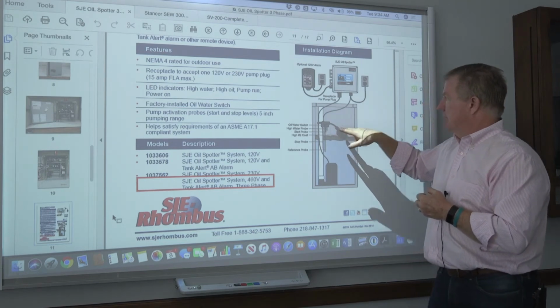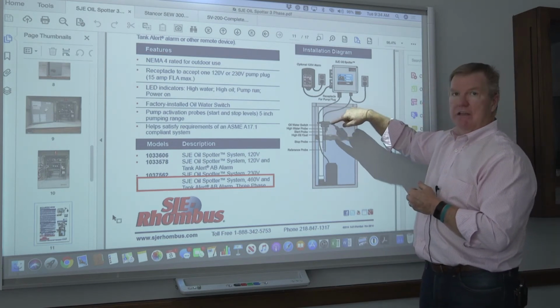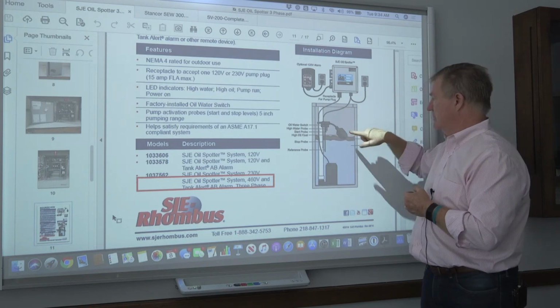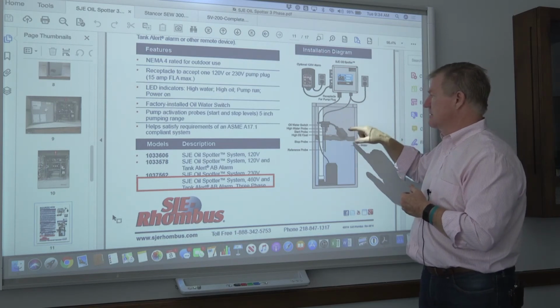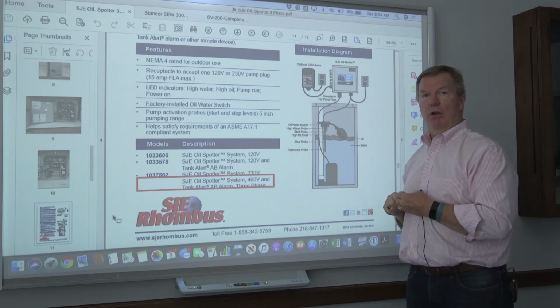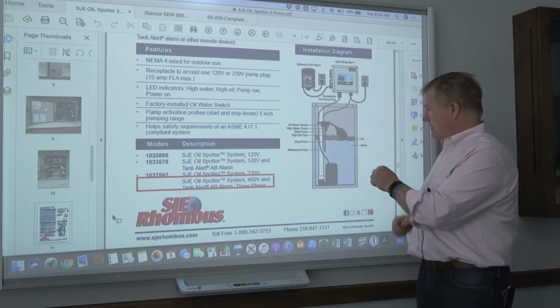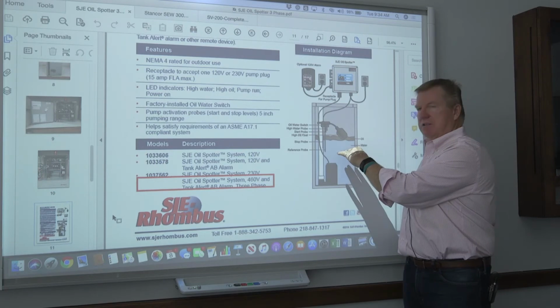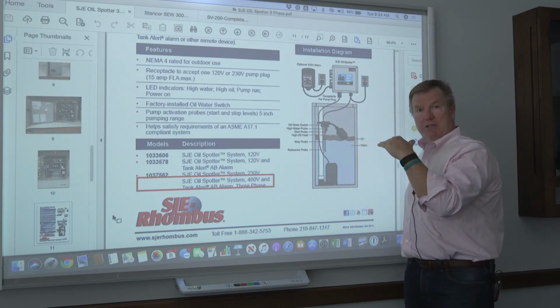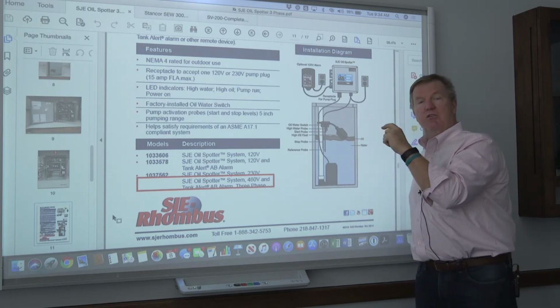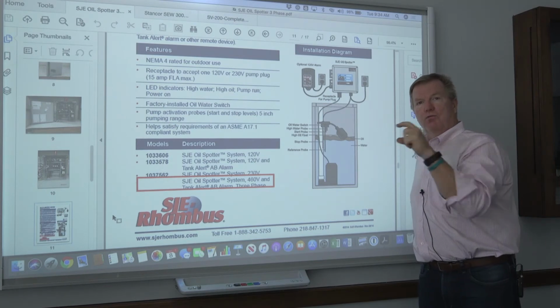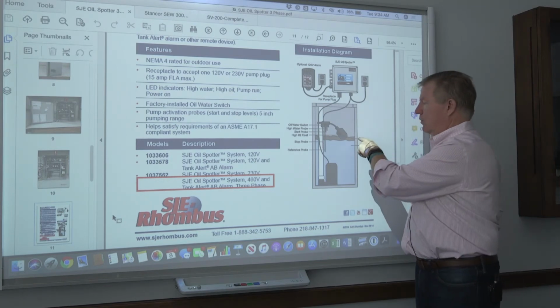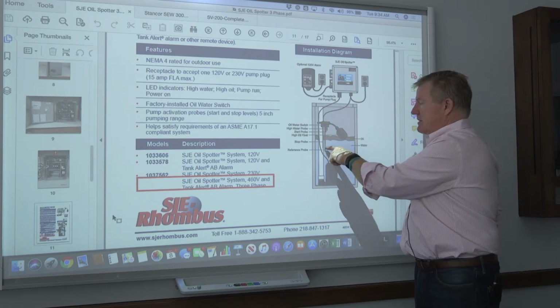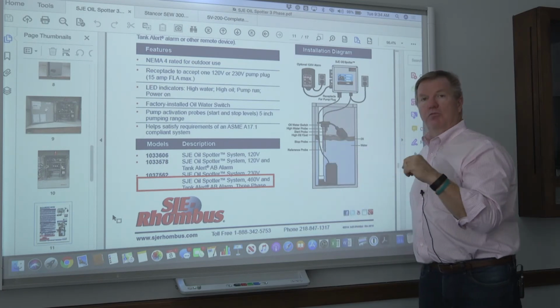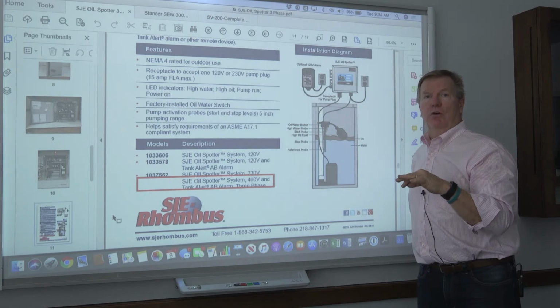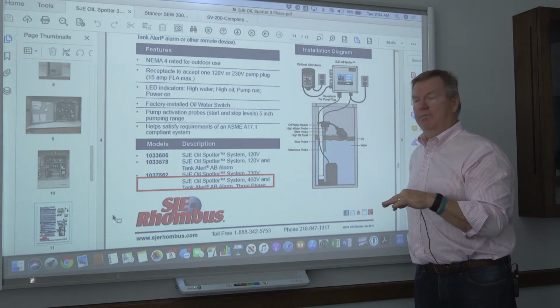The last indicator in the sump is the float, and this is designed specifically for the oil application. So if you have oil in a sump, the oil is going to rise to the top. It doesn't mix with water, so the oil floats on top of the water level, always will stay there. These sensors that you see, the probes, those do not register with oil. They only register with water.